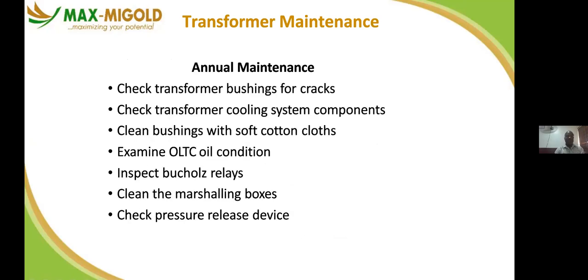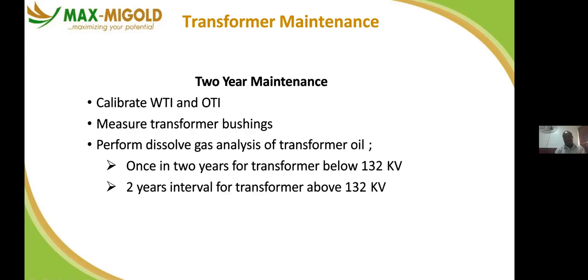So we have the annual maintenance. We check the transformer bushes for crack, check the components, the major ones, if there is any damage, you have OLT, and so on. You clean when appropriate. We have 2 years maintenance, we have winding temperature, oil temperature. So we measure the transformer bushes as well. So these are carried out every 2 years.